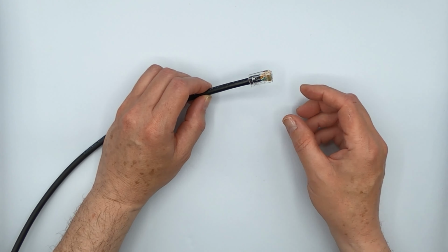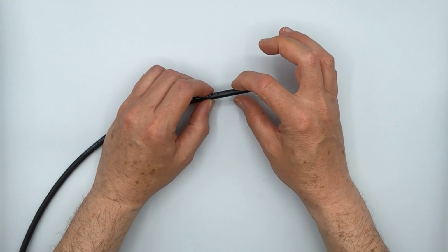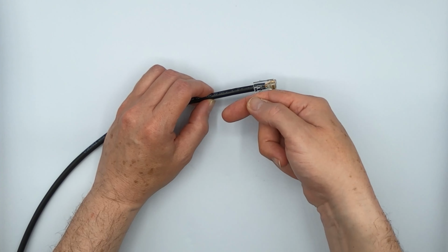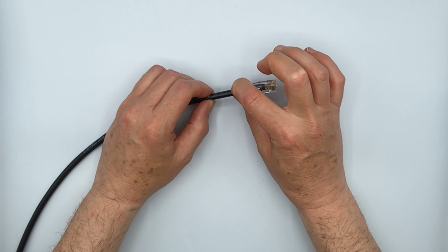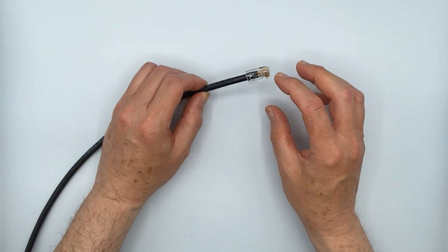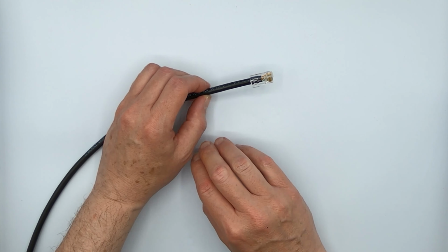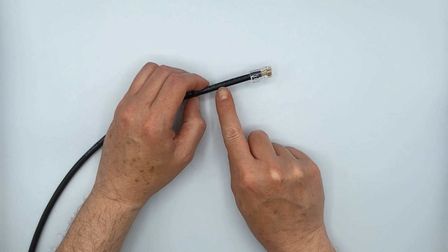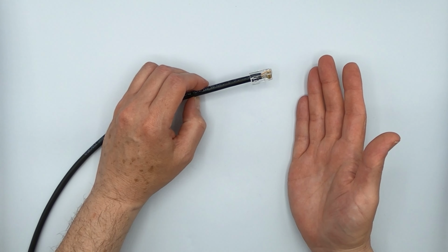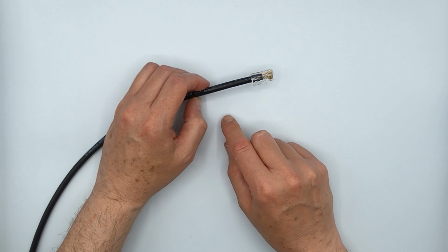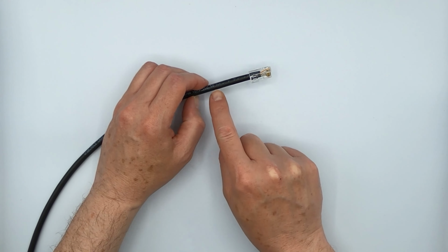But the big advantage of the gel filling is that because the gel filling's all inside the cable and there's not a wrap around it, you're going to have a thinner cable you're dealing with. It's going to be easier to get an RJ45 plug onto it. The other thing is that the gel filling is absolutely impervious to water. So if you should cut this cable jacket and then immerse it into water and come back a day later and test it, it's going to pass every test you can throw at it, assuming you didn't damage the conductors.